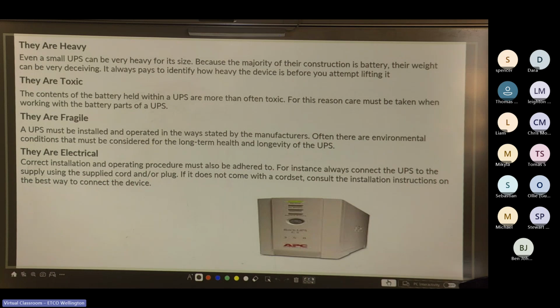Cool. So some things to know about UPSs. They are really heavy. Even a small UPS can be very heavy for its size. Because the majority of their construction is battery, their weight can be very deceiving. It always pays to identify how heavy the device is before you attempt lifting it. They're also toxic. The contents of the battery held within a UPS are more often than not toxic. For this reason, care must be taken when working with the battery parts of a UPS. It's not common yet for them to be lithium ion. It's more common for them to still be lead acid batteries in large scale UPS units. They're generally only lithium ion in the smaller desktop versions.